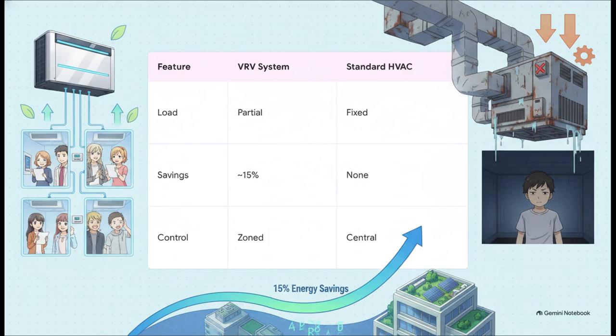When active air conditioning is strictly necessary, the modern system of choice is the Variable Refrigerant Volume, or VRV, system. Unlike conventional HVAC, which wastes a ton of energy on a fixed load, a VRV is highly efficient under partial load conditions. It circulates variable amounts of refrigerant directly to exactly where it's needed, allowing for completely customized individual zoning. Best of all, it entirely eliminates the need for massive plant rooms and heavy chilled water piping and ducting. Overall, a VRV system contributes to roughly 15% energy savings compared to standard central air conditioning baselines.